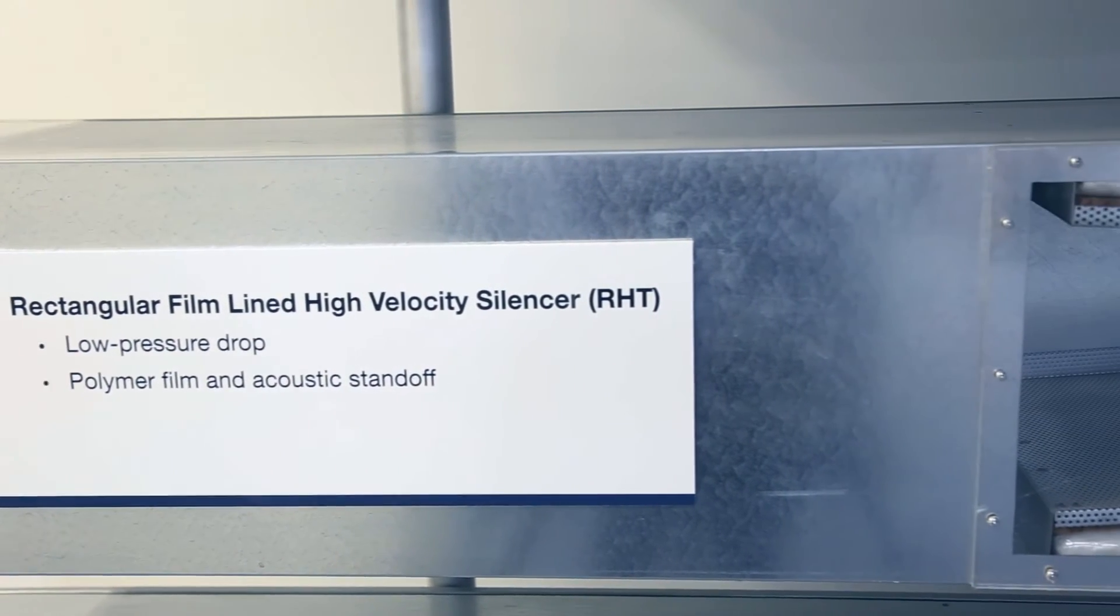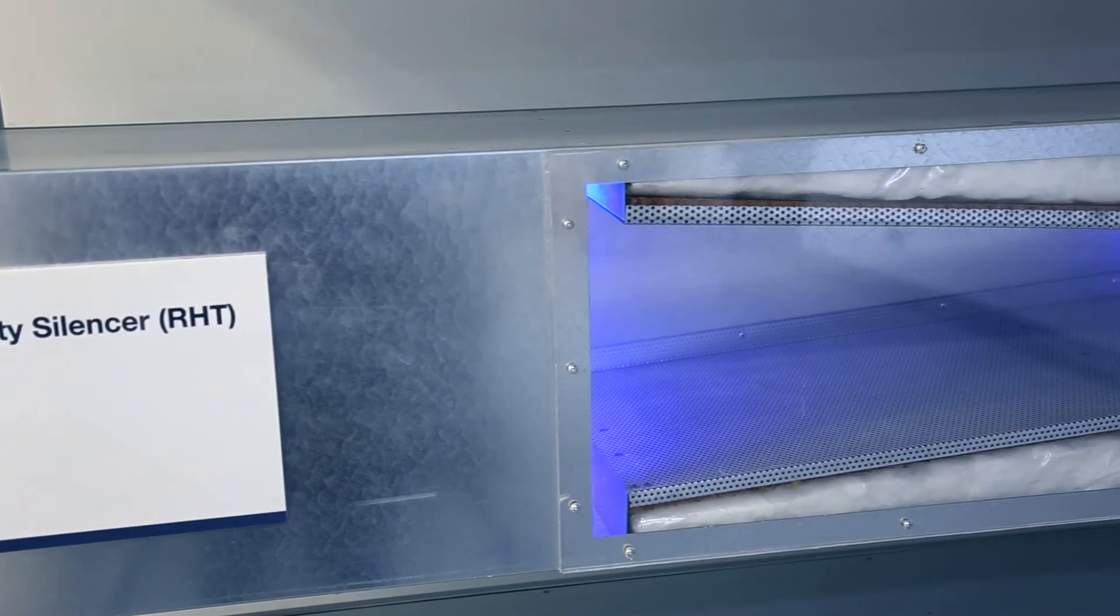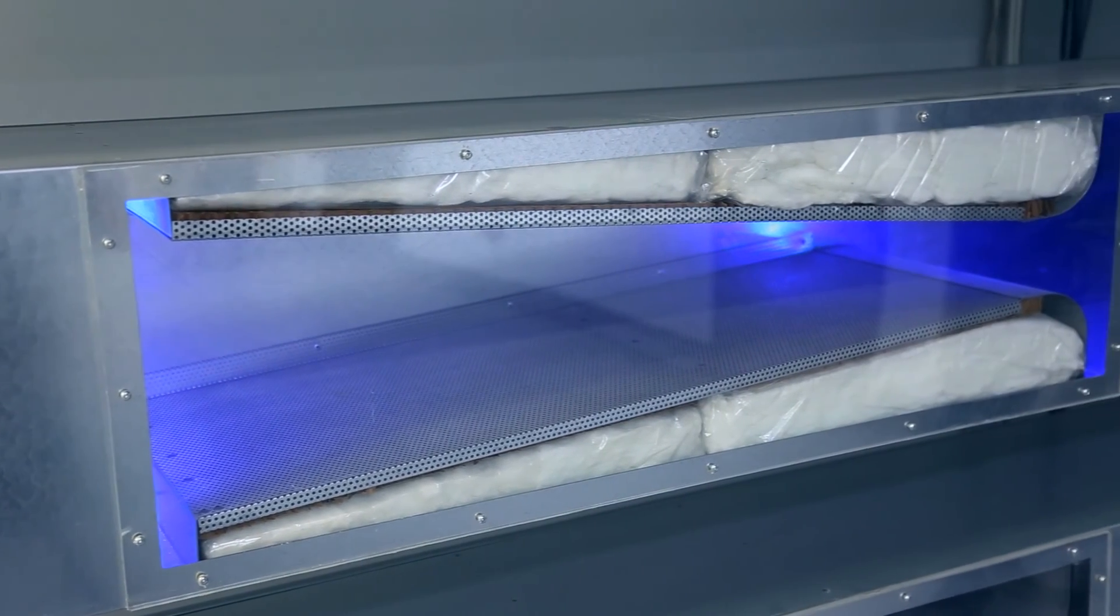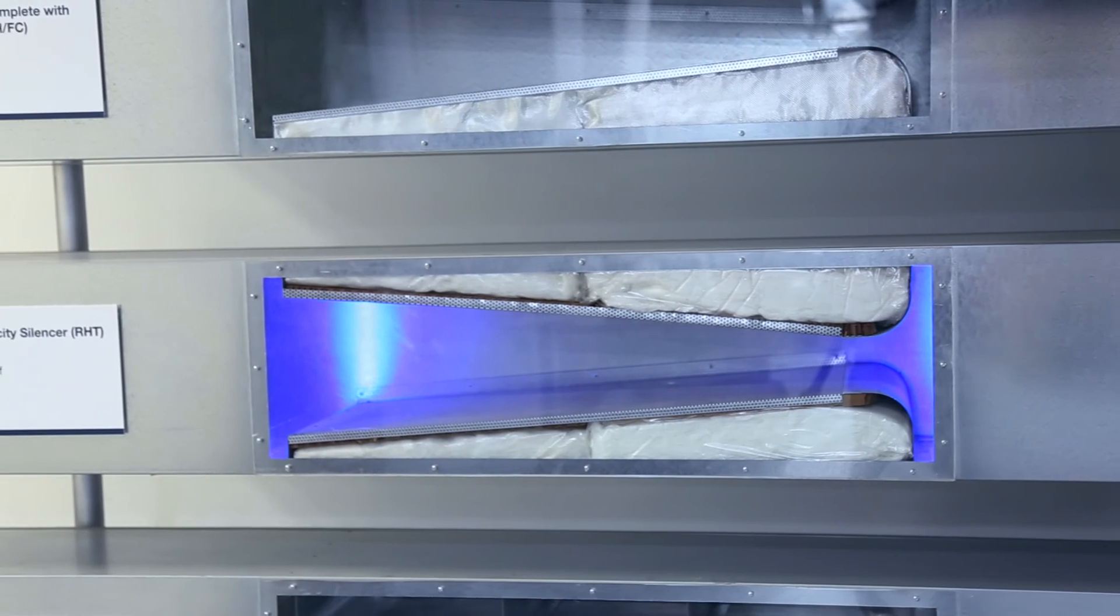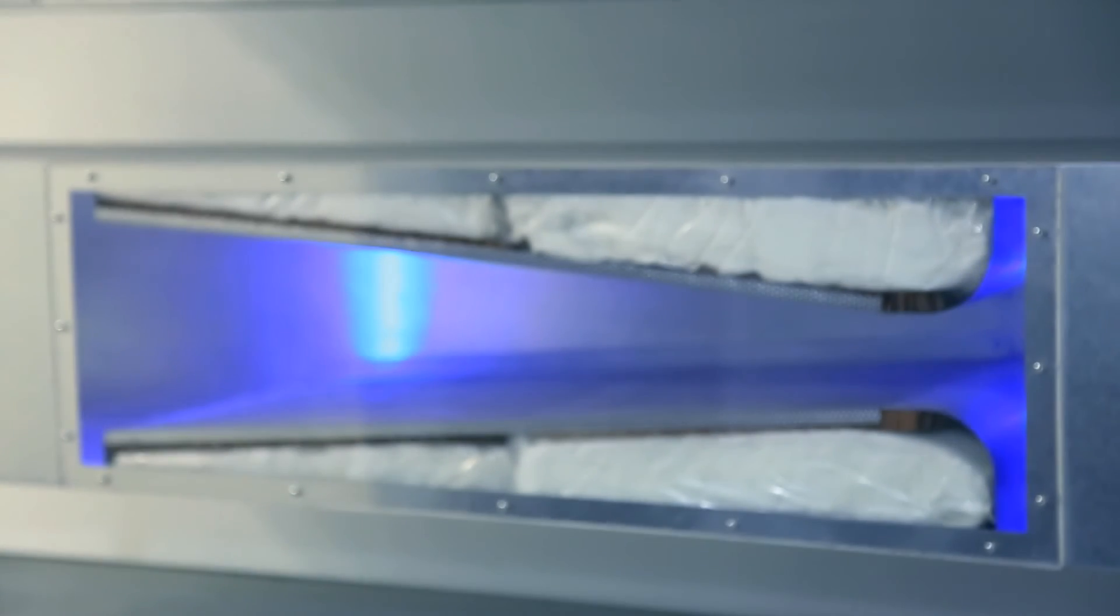The next silencer is a rectangular high velocity silencer with a polymer film liner. Polymer film lined silencers are often used where there is concern with fiberglass from entering the airstream or if there's contaminants in the airstream that you want to protect the acoustic media from. We'll run the sound and airflow measurement through this unit.